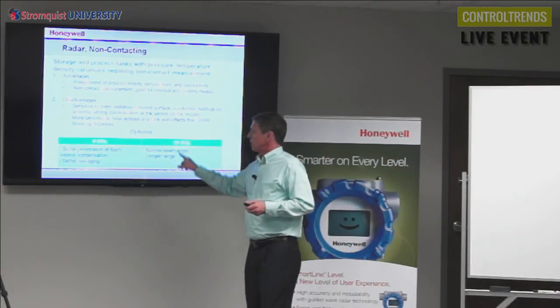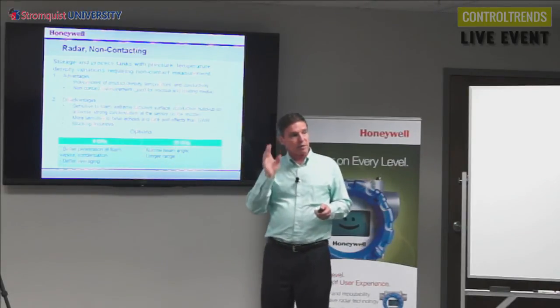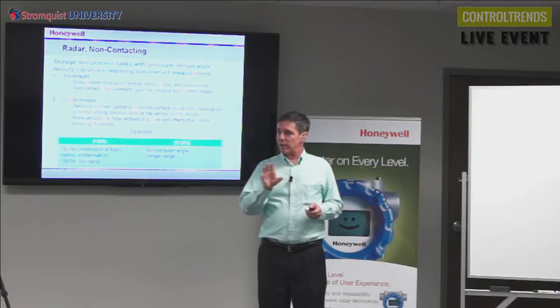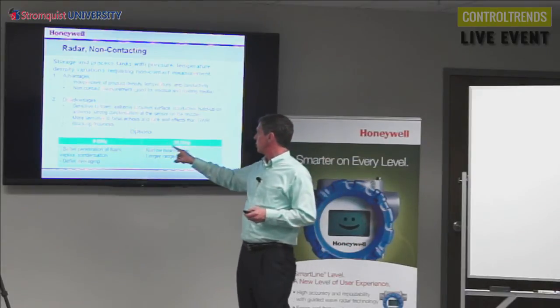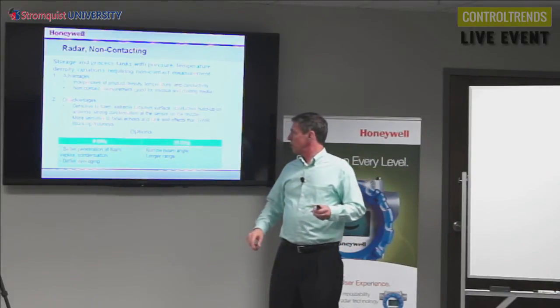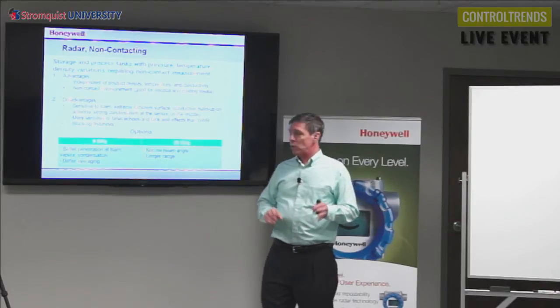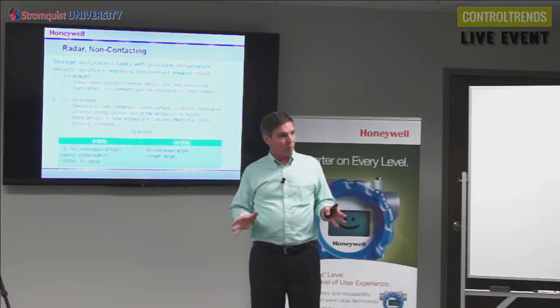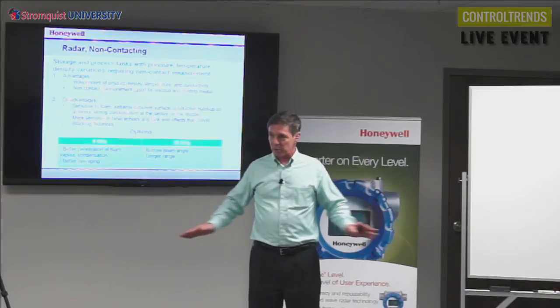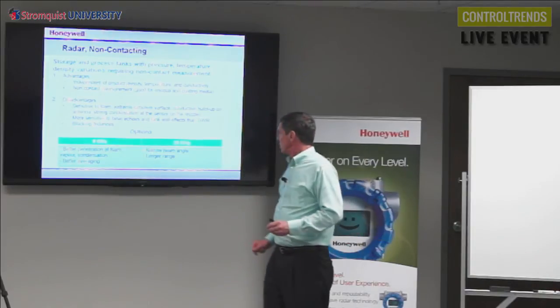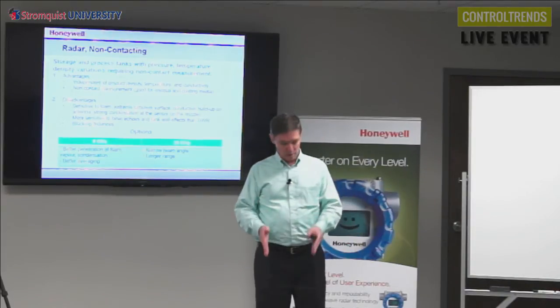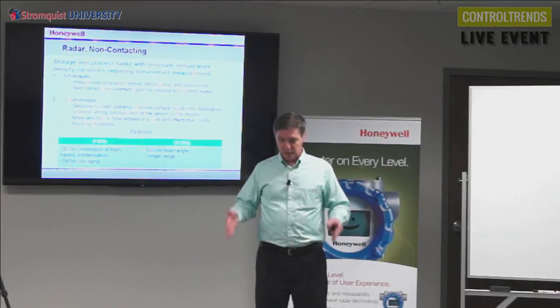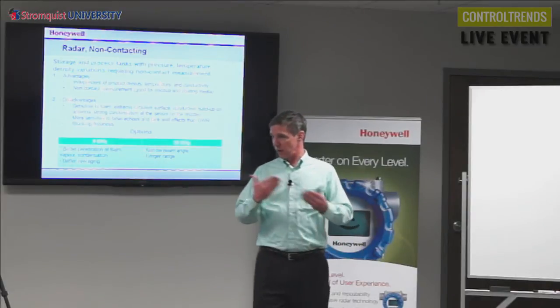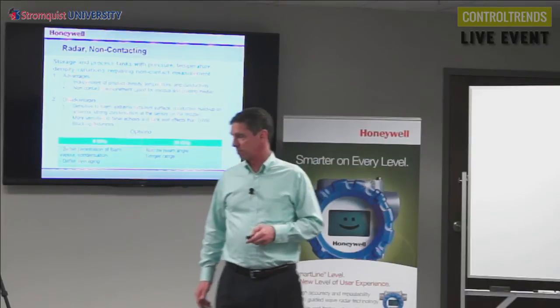And these are the different frequencies. We mentioned this a little bit before, that the non-contacting will have temperature options. The 6 gigahertz versus the 26 gigahertz. The lower frequency, the 6 gigahertz, will do a better job of penetrating foam. However, it's going to be spread out a little bit more. The 26, on the other hand, is going to be more sensitive to foam, and it's going to be a narrower focus. So it kind of depends on the application which way to go with those.